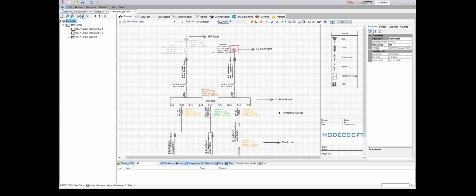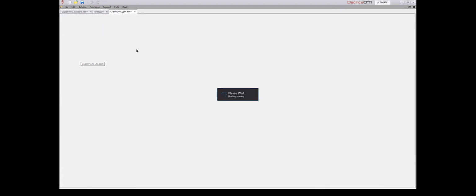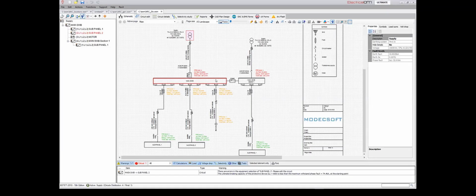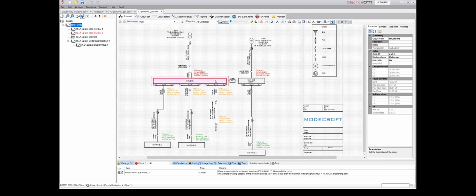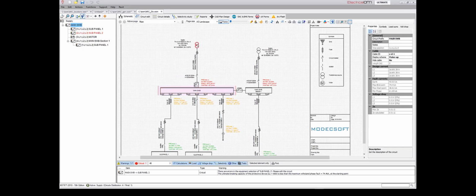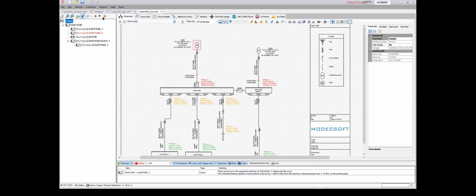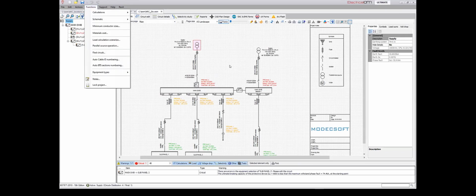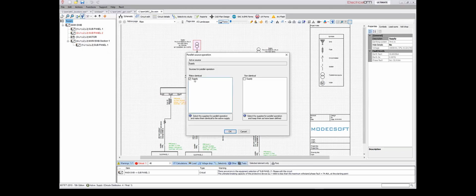So the other thing which is very, very important is when you have parallel source in the network. So transformers, for example, operating in parallel, this will affect your fault levels at the panels, and of course, eventually will affect the arc flash study results. So to make sure that you enable the parallel source operation, you can select the transformer in this case, and of course, the arrangement is supporting this functionality, like in this coupling arrangement. And then by going to the parallel source operation, you can check to use an identical source to parallel those transformers together. Okay.